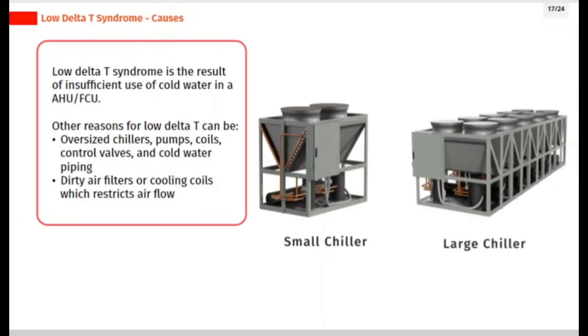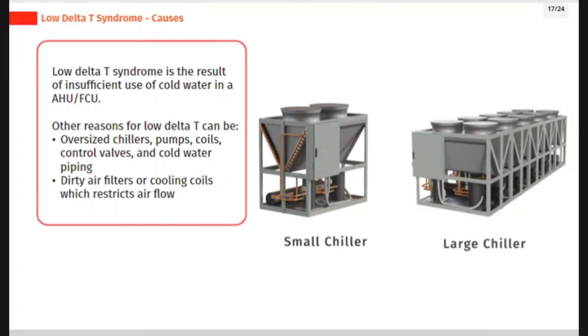Low delta T syndrome is the result of insufficient use of cold water at AHU or FCU. Other reasons for low delta T can be oversized chillers, pumps, coils, control valves, and cold water piping, or dirty air filters or cooling coils which restrict air flow.